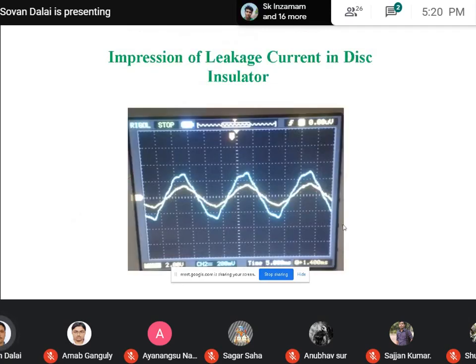And this is one of the impressions of the leakage current. Suppose this is a combination of disc insulators, where this is the overhead high voltage line, and this portion is connected to ground. If we connect an oscilloscope probe in between, we can record the current waveform, since some leakage current is flowing over the surface of the insulator.